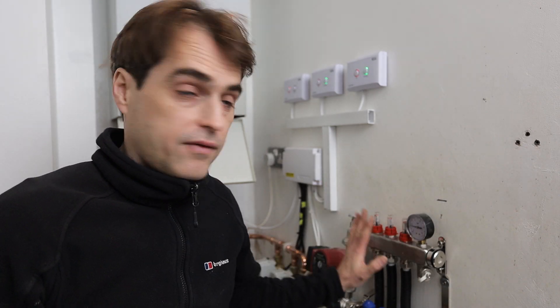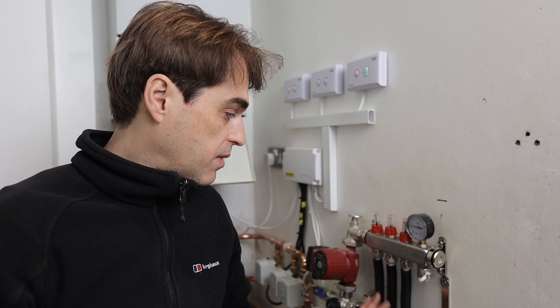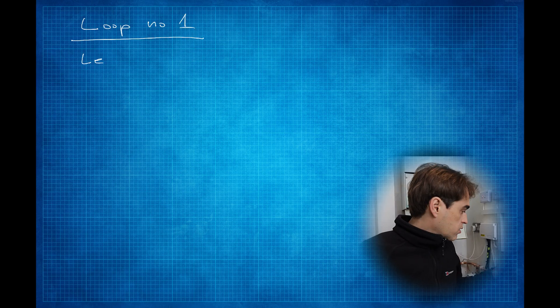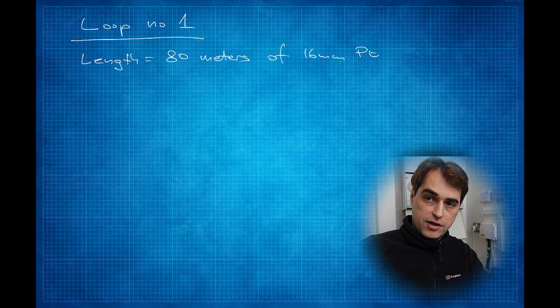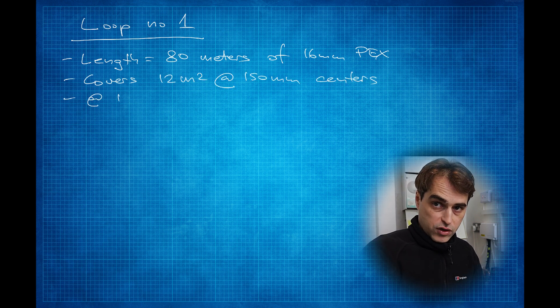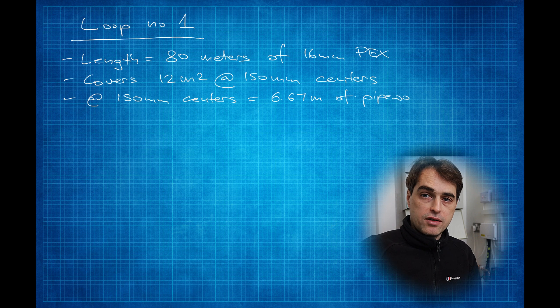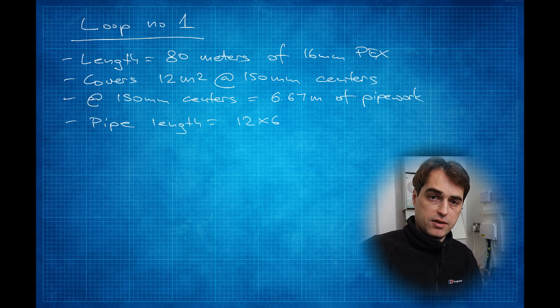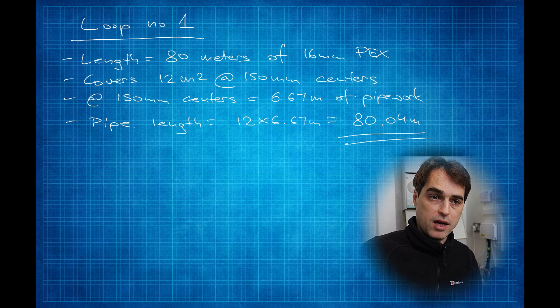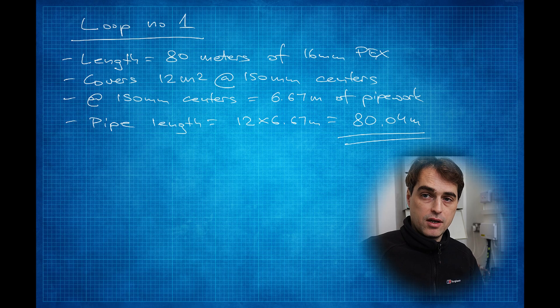To be able to set the flow meters to correct flows, we first have to set the pump. The pump has to do two things: overcome the most restrictive circuit on the manifold — which is the longest length of pipe — and at the same time provide correct flow through all the loops. Our longest loop is loop number one at 80 linear meters of pipework, covering 12 square meters at 150mm pipe centers.